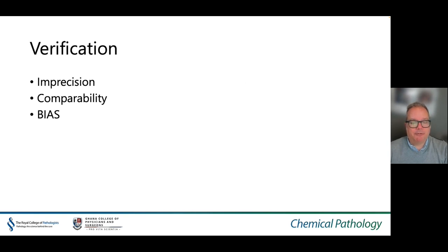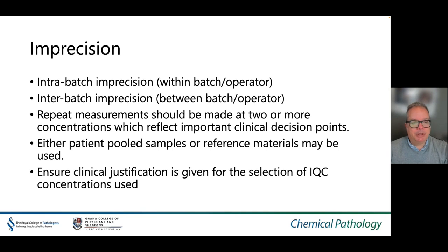In terms of the minimum required for a verification, imprecision, comparability, and assessment of bias should be performed. Imprecision includes intrabatch imprecision (within-batch) and interbatch imprecision (between-batch), both of which can be measured and determined. Repeat measurements should be made at two or more concentrations which reflect clinically important decision points, using patient pooled samples or reference materials. Clinical justification is required for the selection of IQC concentrations, which are usually around important decision points with the method.